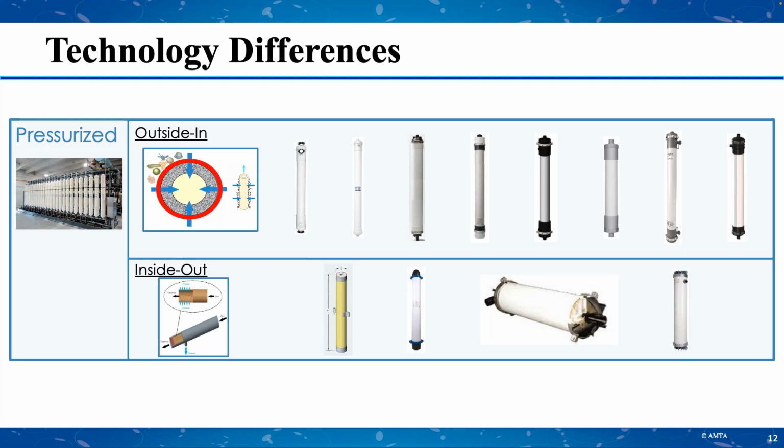Then on top of that, you have different port configurations. So some have a feed which enters at the bottom center. Some have one that comes in through the bottom side. Then you have the same sorts of differences on the filtrate port, being from the top center or the top side, and the backwash waste or air vent, same thing, top center or top side.